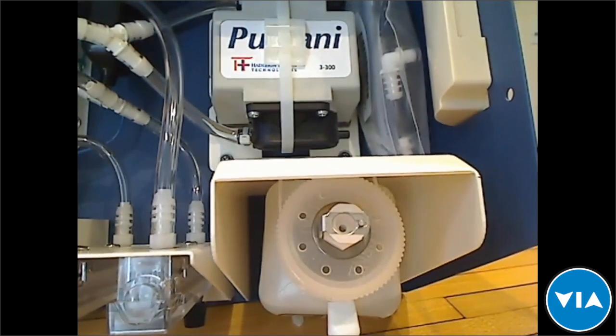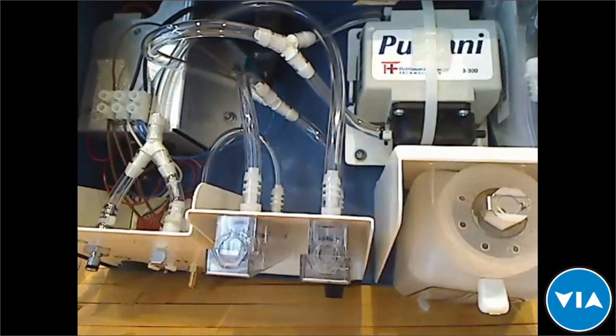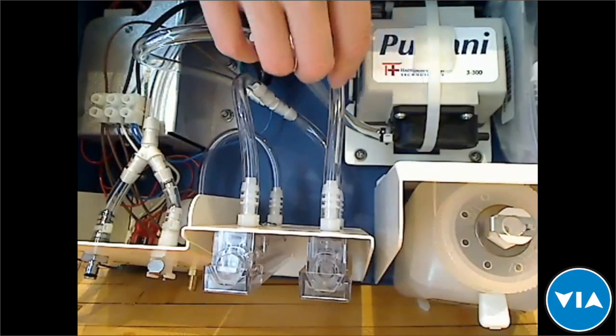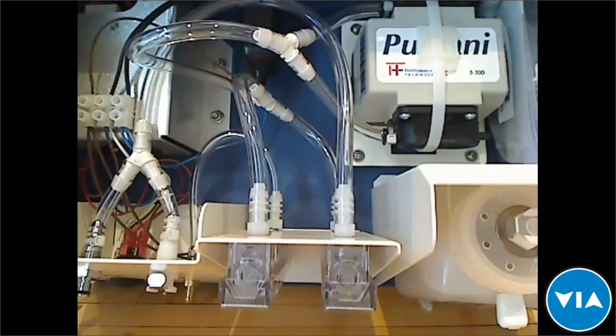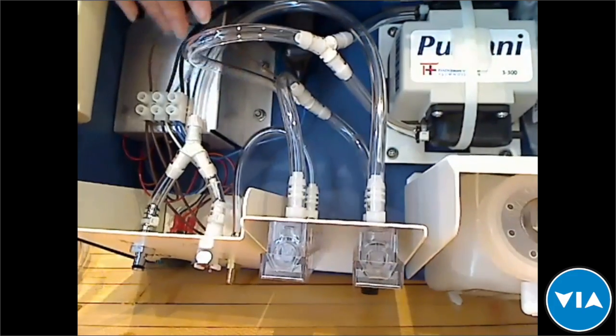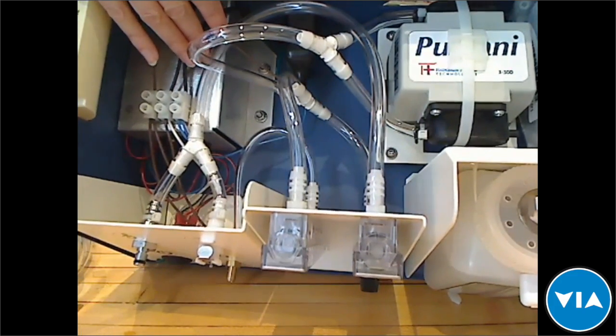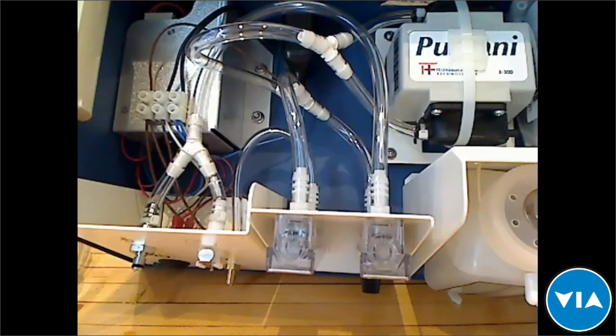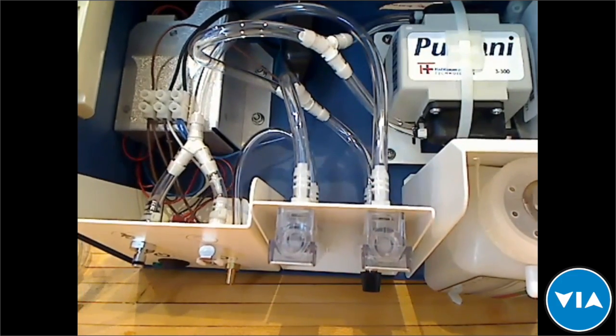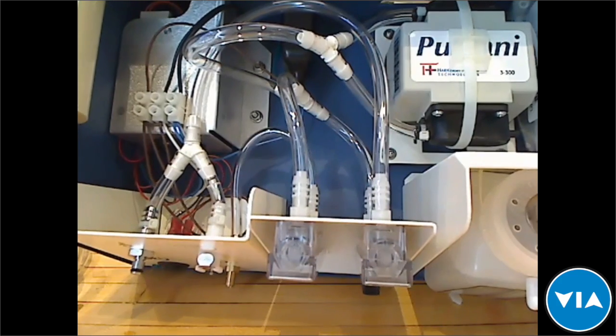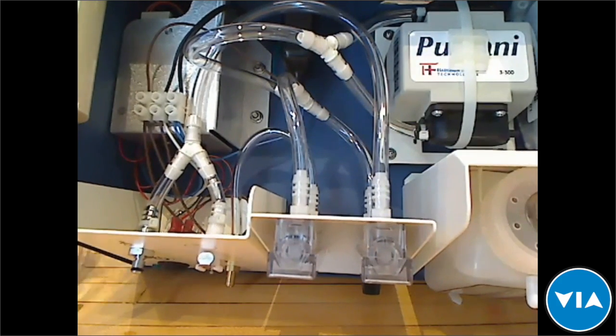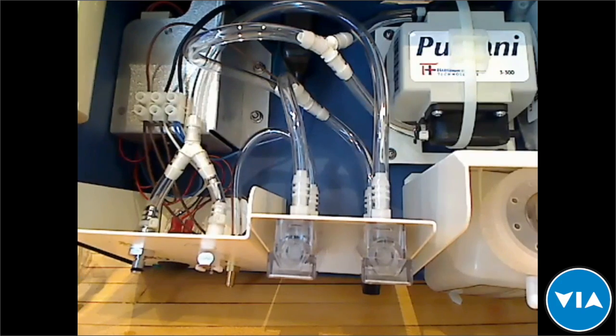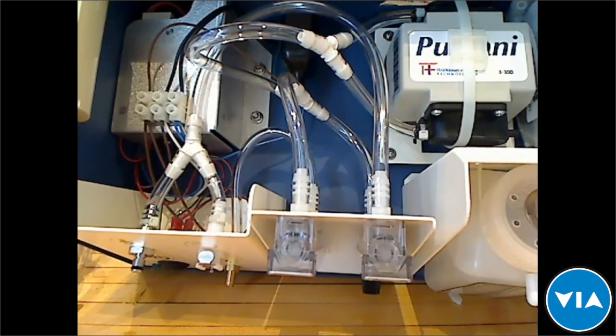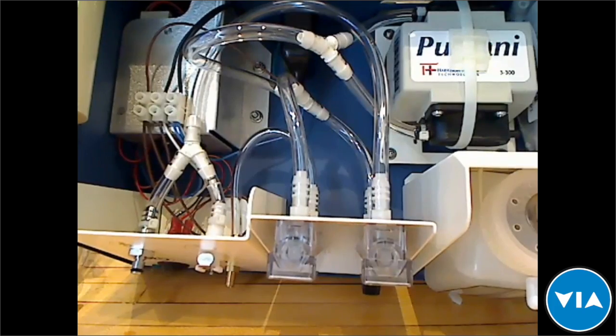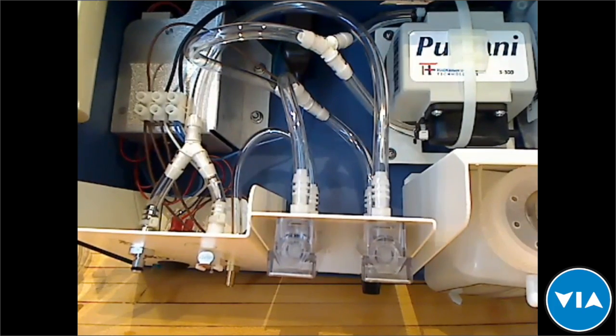Occasionally this tubing can become disconnected, so that may be a common issue, but it's very easy to go into the machine and just reattach the tubing. We also have an electronics box back here, and that is an alarm for the system that will sound after 10 seconds if power is lost to the unit. So that alerts the user that the baby is not receiving therapy, the machine is not currently working, and typically we recommend that the baby go on oxygen if it's available until power returns to the ward.